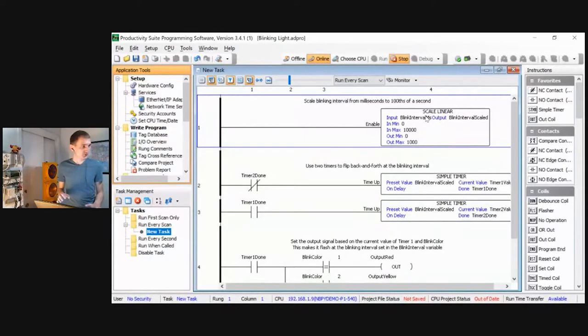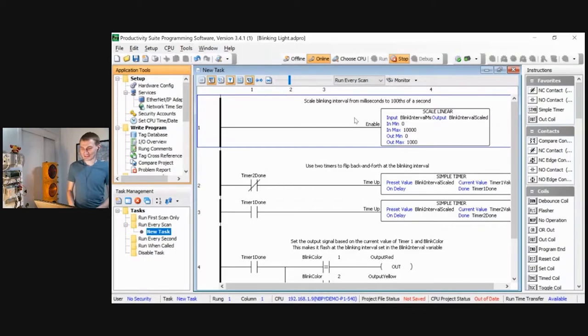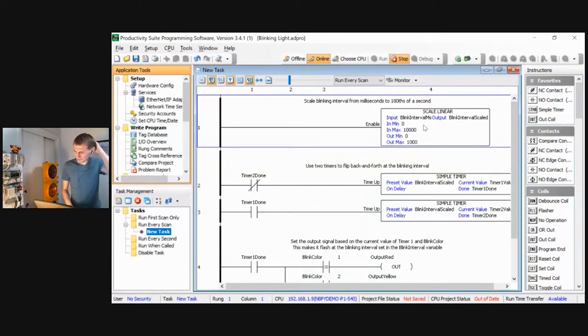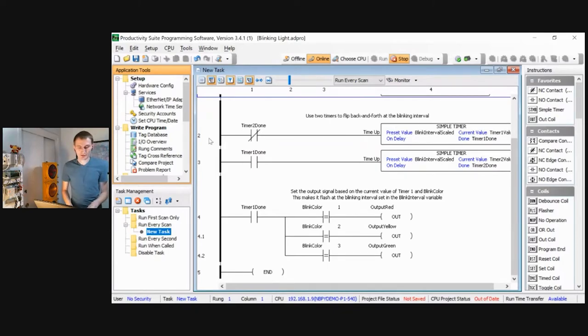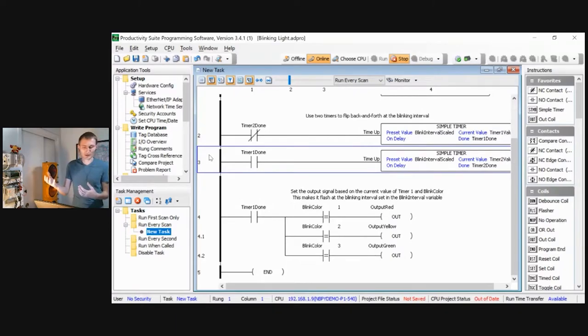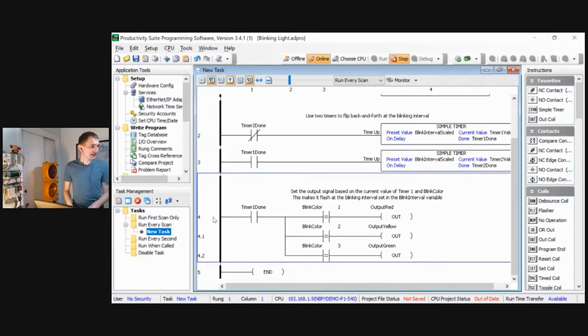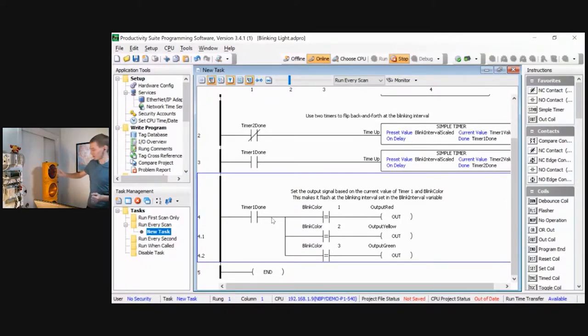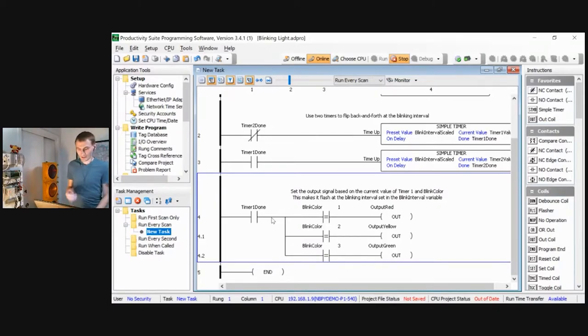In the first row you'll see a variable called blink_interval_millisecond, which is the millisecond value for how fast to blink — the code scales it to an internal value. Lines two and three are timers: one for how long the light is on, one for how long it's off. The final line uses a variable called blink_color, which drives which output signals get energized: if blink_color equals 1, red blinks; if 2, yellow blinks; if 3, green blinks. Those are the two variables we care about: blink_interval_milliseconds and blink_color.